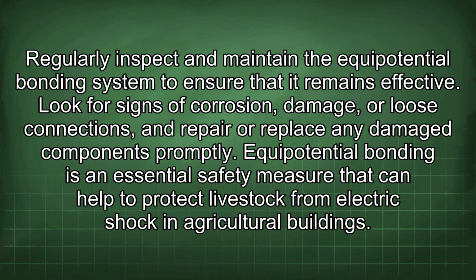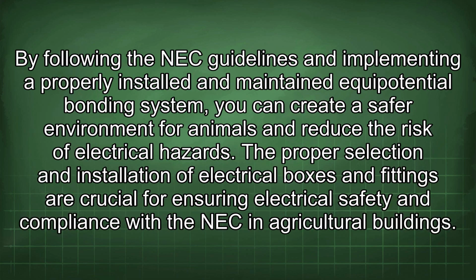Regularly inspect and maintain the equipotential bonding system to ensure that it remains effective. Look for signs of corrosion, damage, or loose connections and repair or replace any damaged components promptly. Equipotential bonding is an essential safety measure that can help to protect livestock from electric shock in agricultural buildings. By following the NEC guidelines and implementing a properly installed and maintained equipotential bonding system, you can create a safer environment for animals and reduce the risk of electrical hazards.